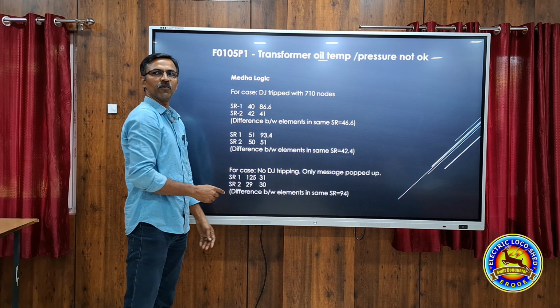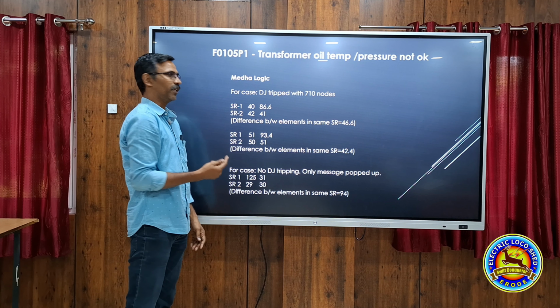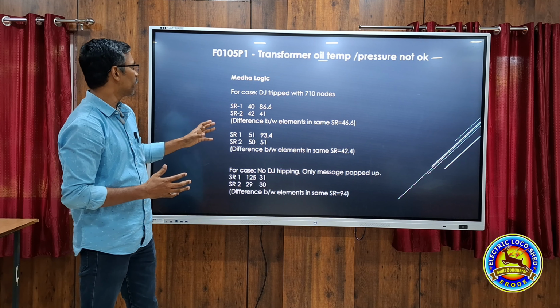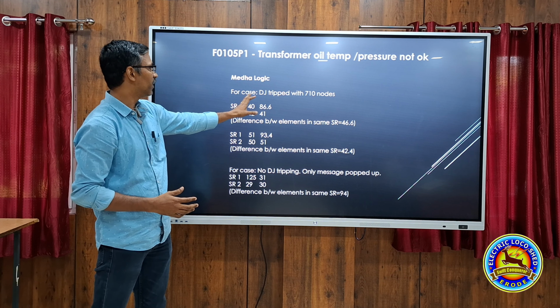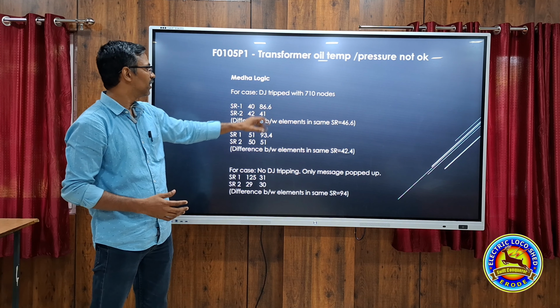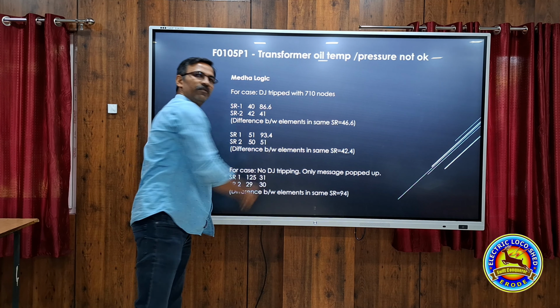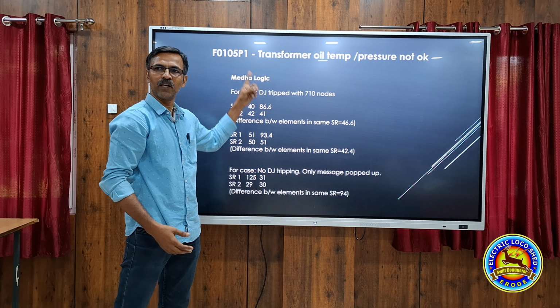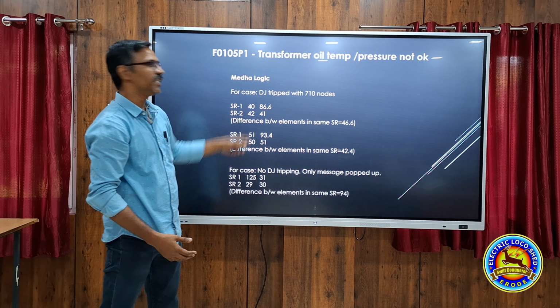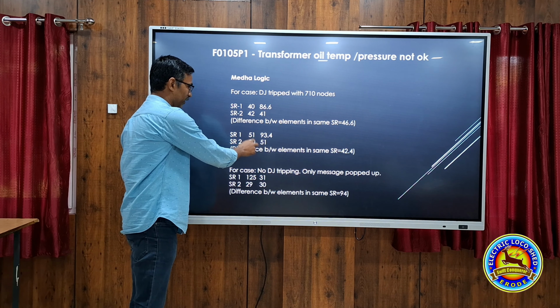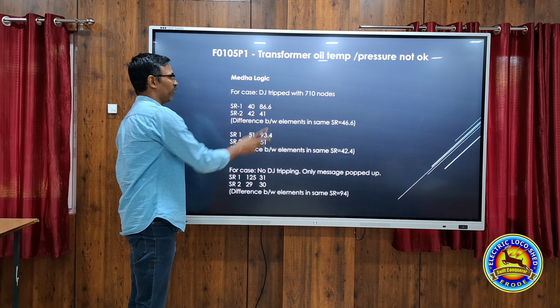But one sensor is malfunctioning. One element is malfunctioning. But the difference you can see is 46.6, so it is within the 50 degree difference only. So the DJ will trip because the value reached beyond 84, and the difference is within 50 only. So this value will be considered for tripping the DJ. The DJ will trip and the notch will go to 710. This is another case, the same situation. The temperature difference is different. The value is correctly around 50 or 51, but one sensor is malfunctioning.